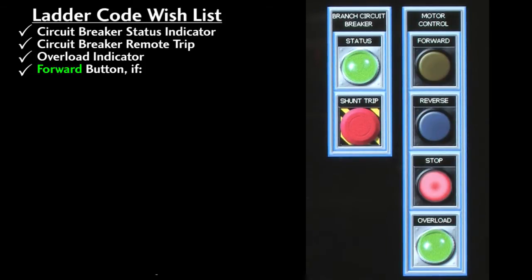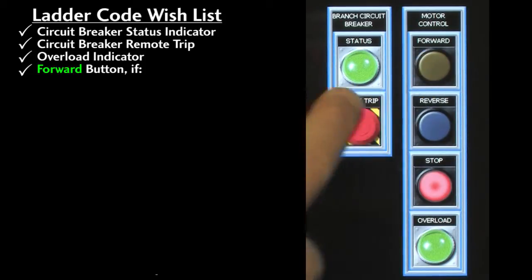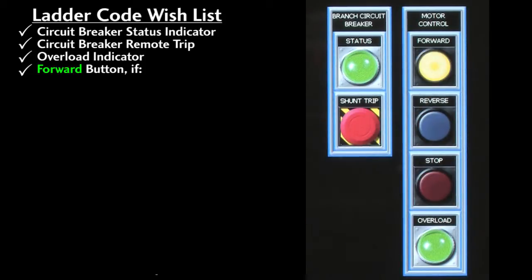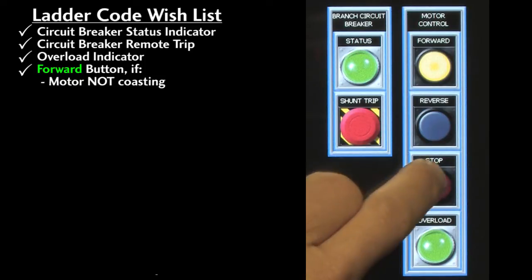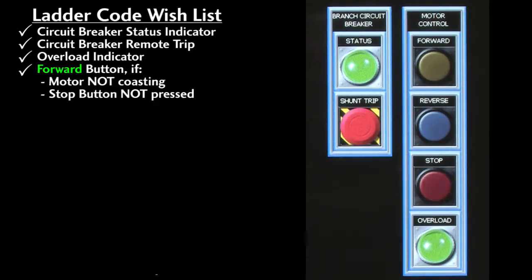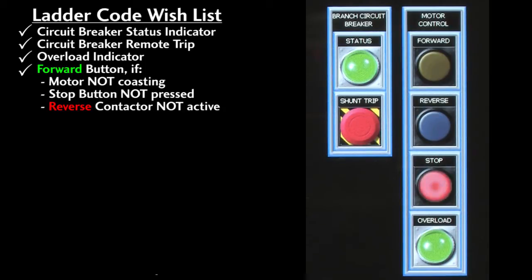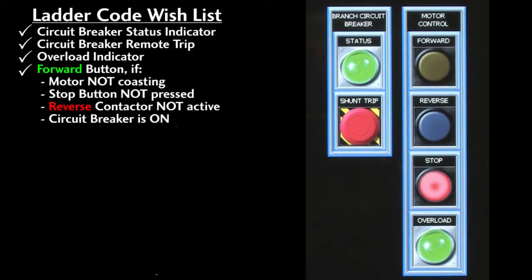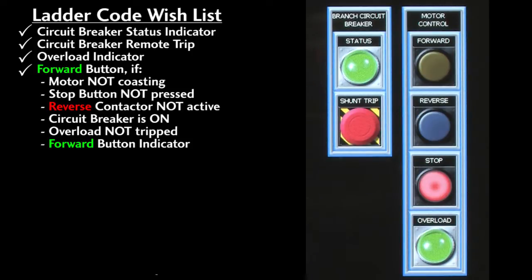On the forward button press we want to start the motor in the forward direction if the motor is not coasting, if the stop button is not being pressed, if the reverse contactor isn't engaged, if the circuit breaker is on, if the overload is not tripped, and we'll want the forward indicator lit while the motor is running.